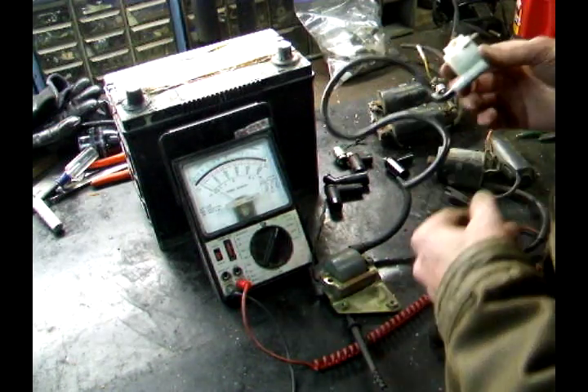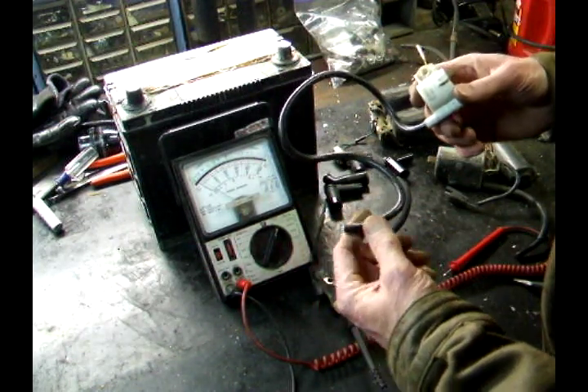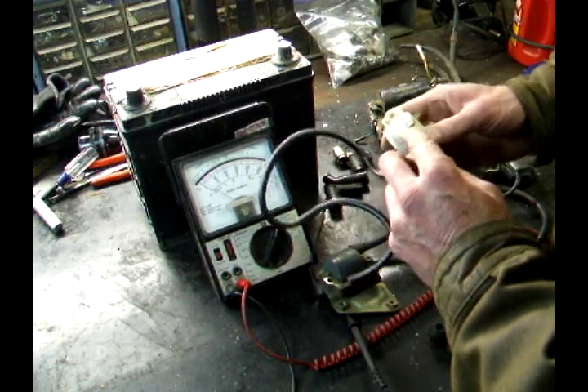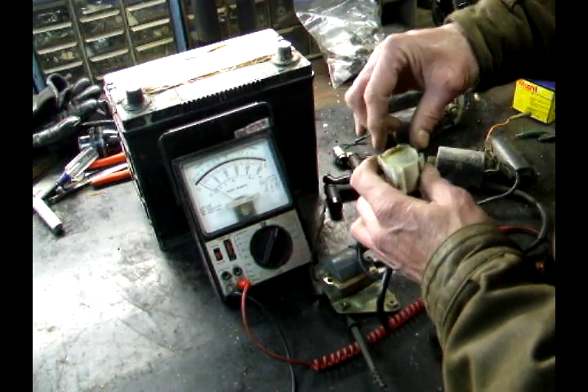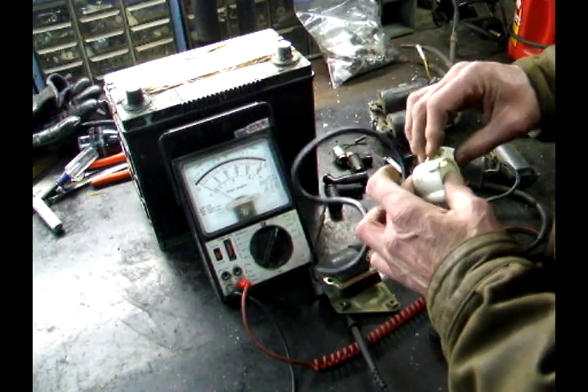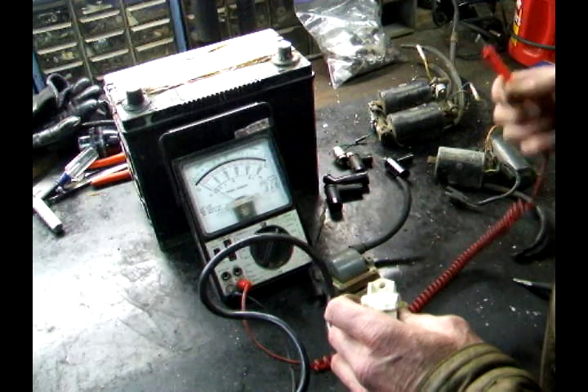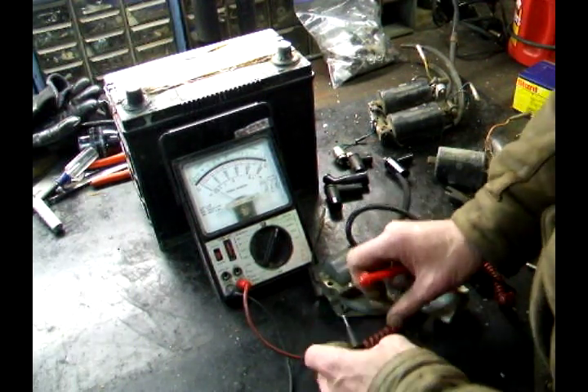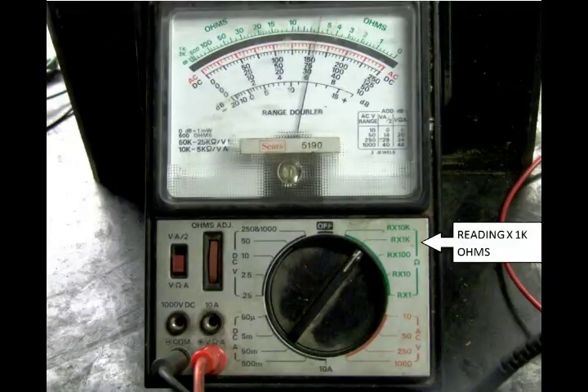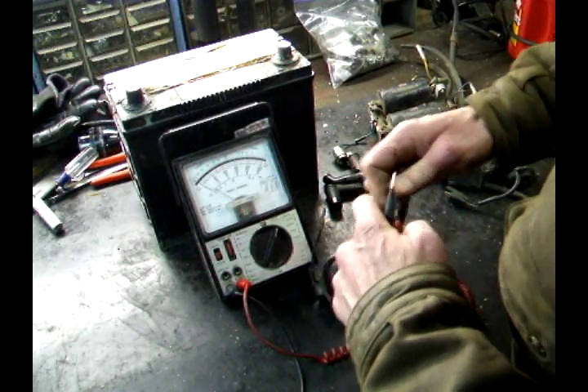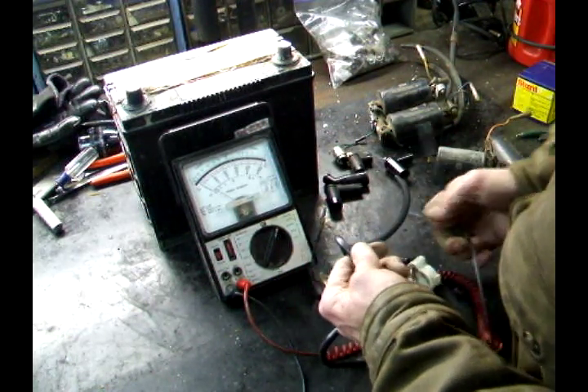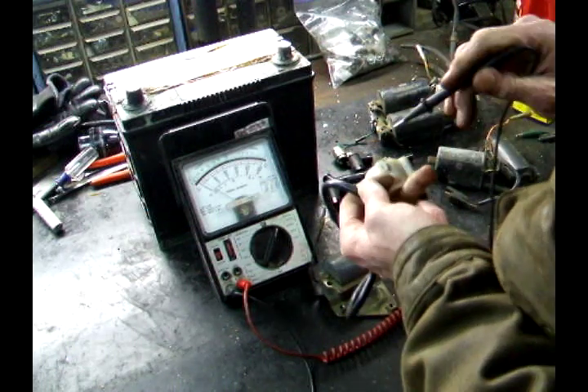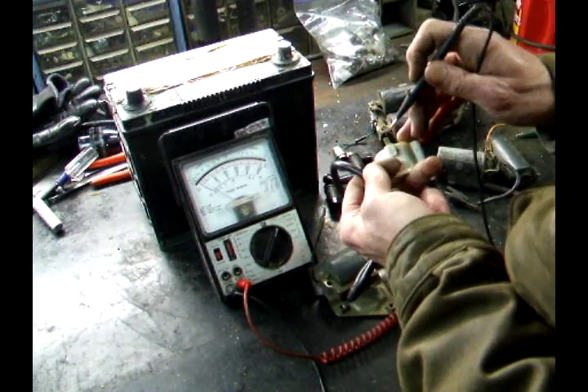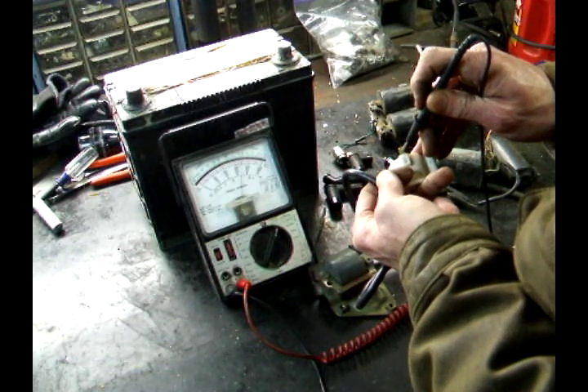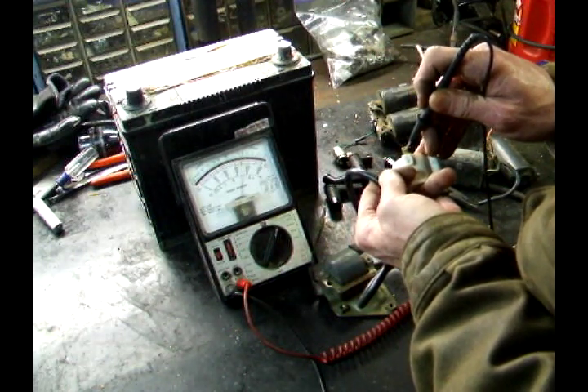Here's the moped one. To test that, this is the high voltage coil, and usually these are marked. It's the low voltage terminals, and one of these is connected to the high voltage terminal. And you can test that. We'll do that now. We got the settings on 1,000 ohms, so we poke the lead in the end and test. This thing has a mark where it says ground or earth. And if you test it, it comes up about 4,500 ohms.